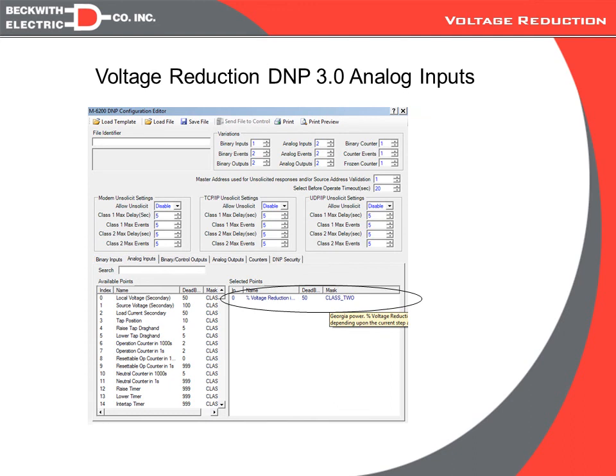And finally, we have an analog input that shows you when it's in reduction what percentage is being applied. And from that, you can know what level. So if I were in level 2 and level 2 was set to 5%, I would be getting back the value of 50 on this particular point and do a divide by 10, and it would show me that there's currently a 5% reduction being applied.